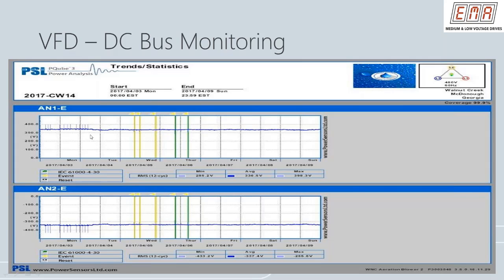we saw some high-speed noise riding on top of our DC bus. Just to give you an idea how drives are designed, on our IGBT section, when the IGBTs turn on and off, they produce a significant amount of noise or overshoot. Now, this overshoot or noise is filtered by a snubber filter. We have a snubber network of resistors and capacitors inside the drive, and their job is to filter out high-speed switching noise that is generated by the IGBTs. Then what happened in this case, as those snubber networks start to fail because of age and heat, you can see they're not able to do their job effectively.